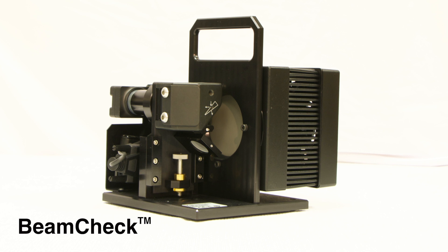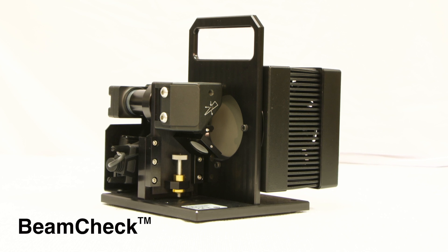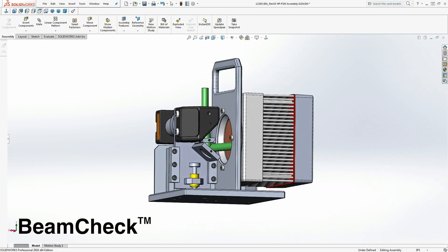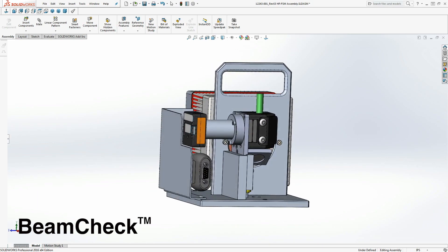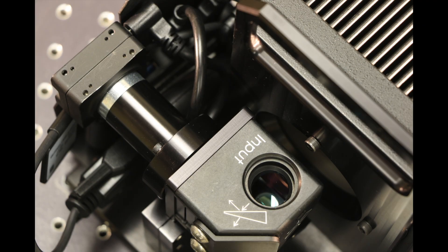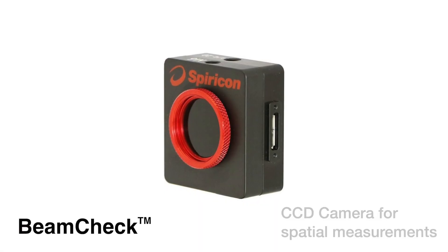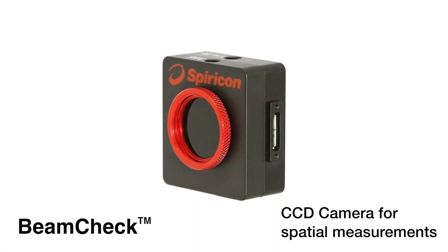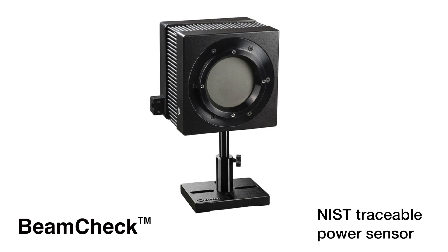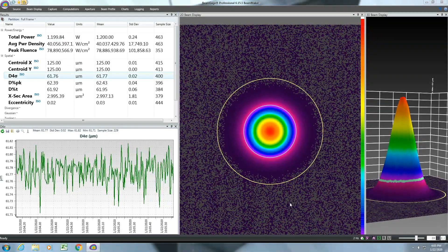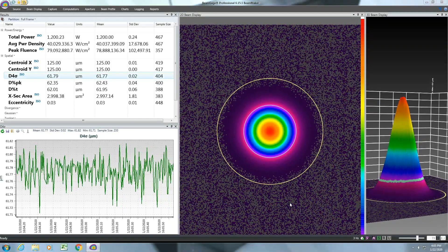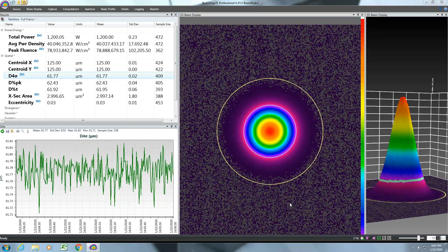Ophir Spiricon introduces BeamCheck, an integrated laser measurement system designed to measure critical laser beam parameters for laser-based additive manufacturing systems. BeamCheck includes a CCD camera for spatial measurements and a NIST traceable power sensor that will provide a complete analysis of the laser power density profile.